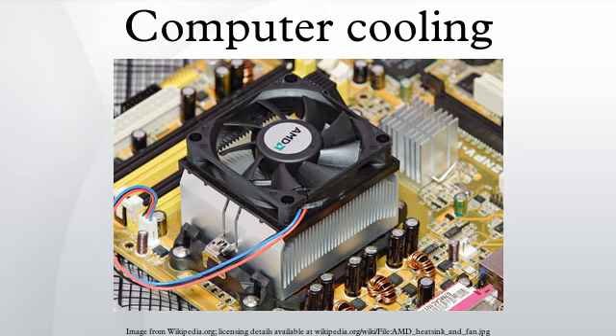Fans generally have two published specifications, free airflow and maximum differential pressure. Free airflow is the amount of air a fan will move with zero back pressure. Maximum differential pressure is the amount of pressure a fan can generate when completely blocked. In between these two extremes are a series of corresponding measurements of flow versus pressure, which is usually presented as a graph. Each fan model will have a unique curve, like the dashed curves in the adjacent illustration.